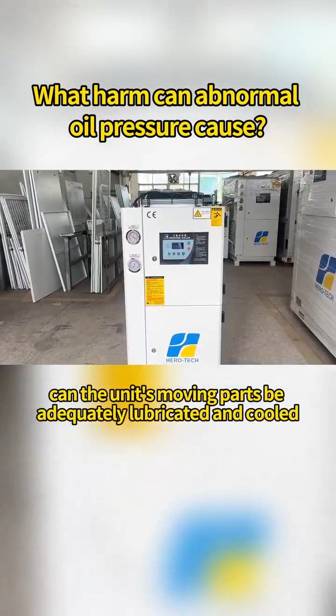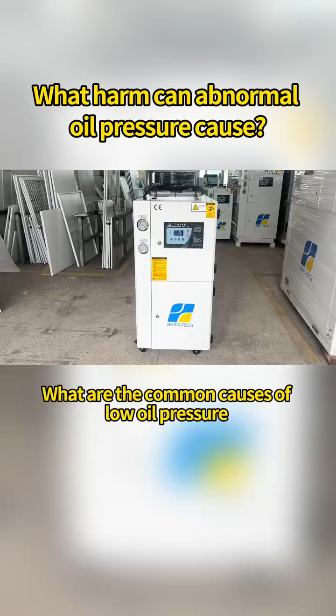Only when the oil pressure is normal can the unit's moving parts be adequately lubricated and cooled. What are the common causes of low oil pressure in a refrigeration unit? These include a damaged oil gauge, clogged oil lines, excessive clearance in the oil pump, and excessive refrigerant in the oil.